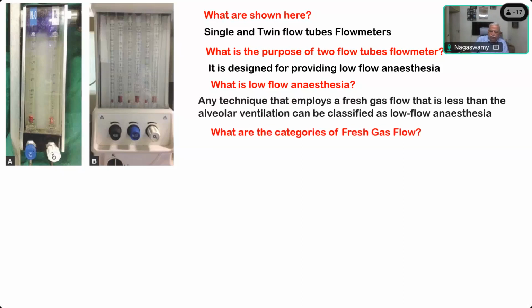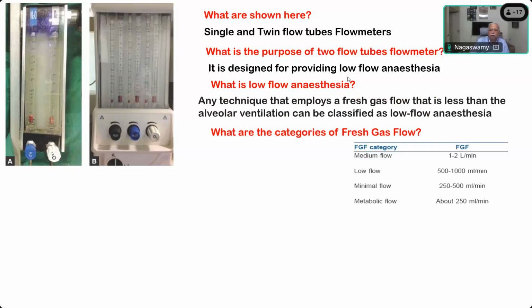What are the categories of fresh gas flow? How do you classify fresh gas flow? Medium flow is 1 to 2 liters. Low flow is 500 to 1000 ml per minute. Minimal flow is 250 to 500 ml per minute, and metabolic flow is about 250 ml per minute.